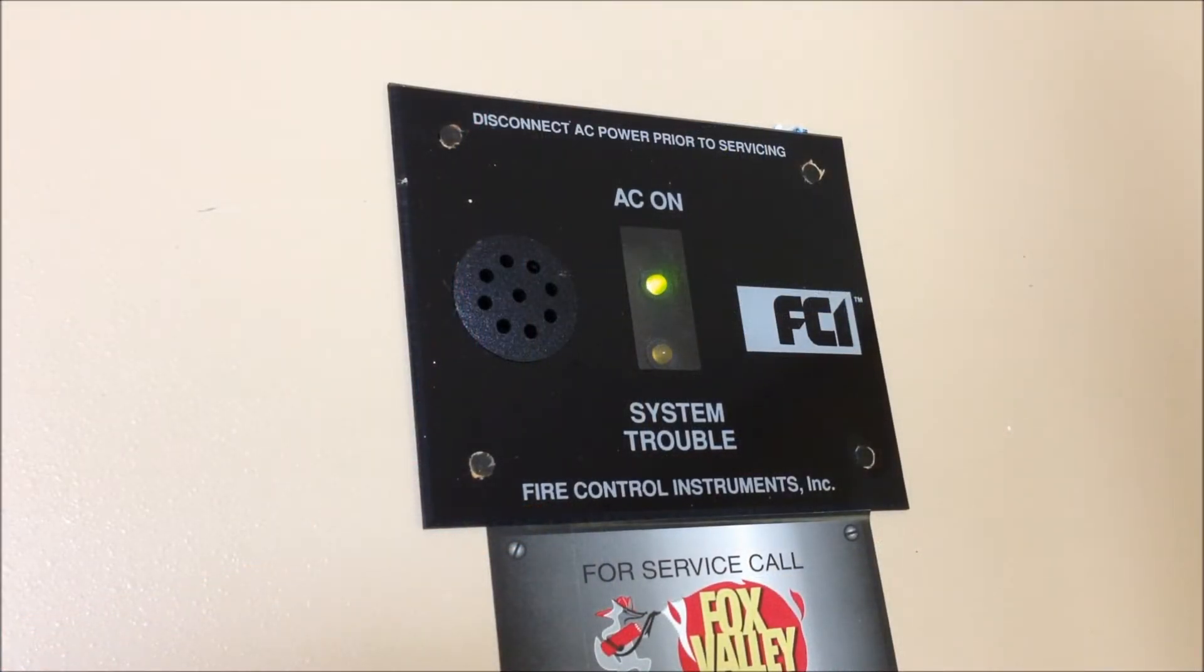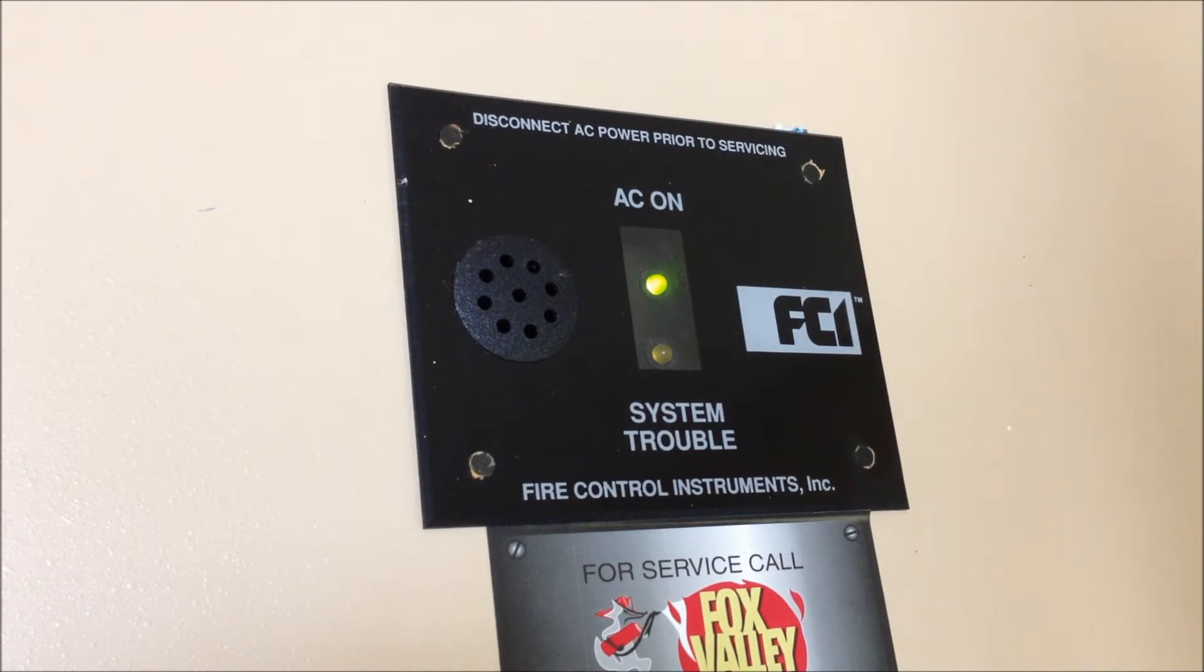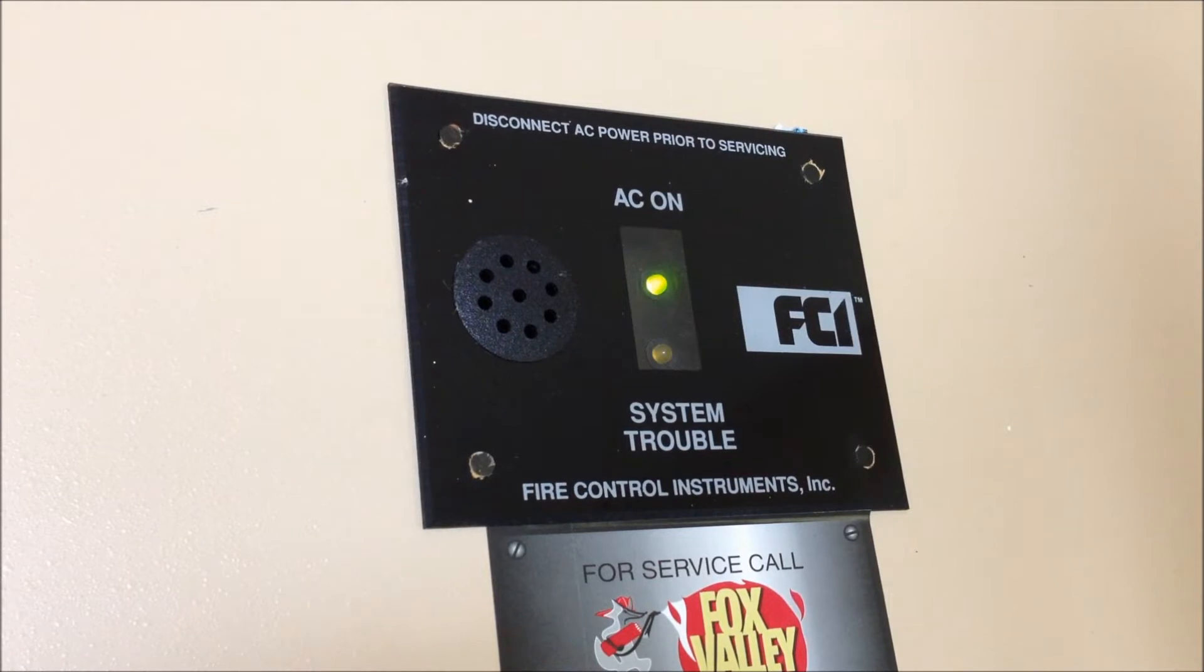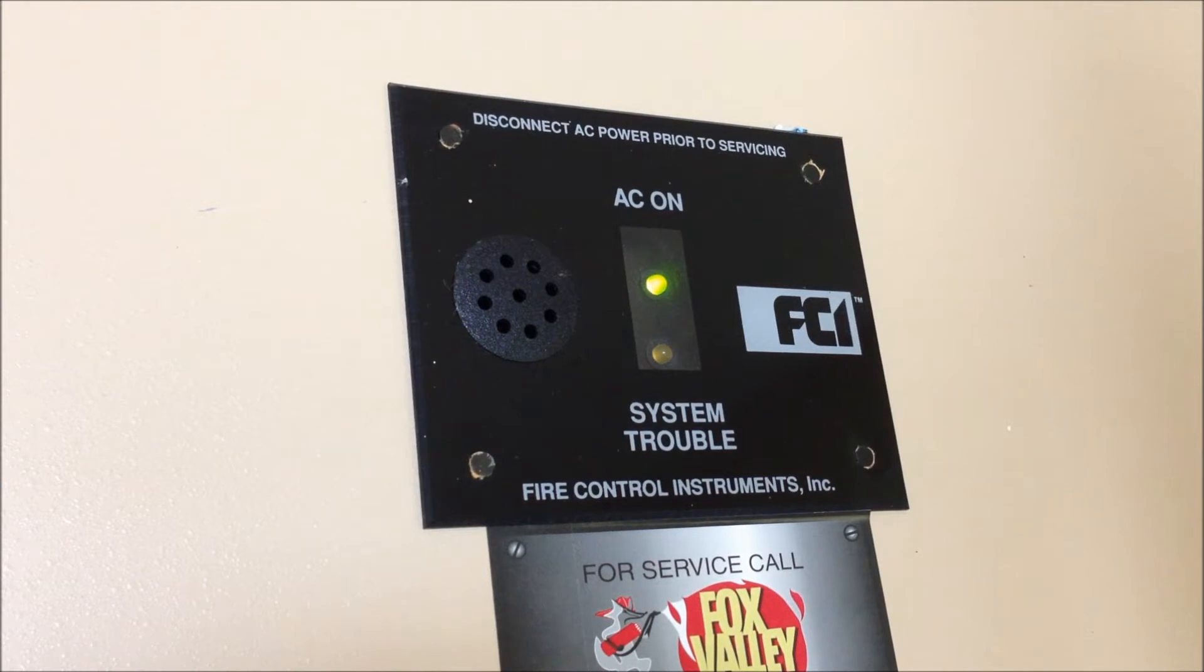Looking first at the main display window on the FC-72 you can see that we have AC power and no troubles in the system and you can also see a little bit lower down on the panel there's a sticker from Fox Valley Fire and Safety they used to service this panel when it was installed.